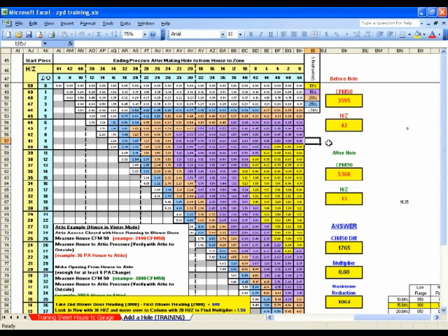The numbers that we took during this example, we were starting out at 42, we moved across to 13, we were out in this purple zone. We can't get into the gold zone when we're starting out at 42 because we can't move over far enough. So in order to get in the gold zone, our starting pressure needs to be somewhere between 25 and 40. So how are we going to, in this case, get into that zone?